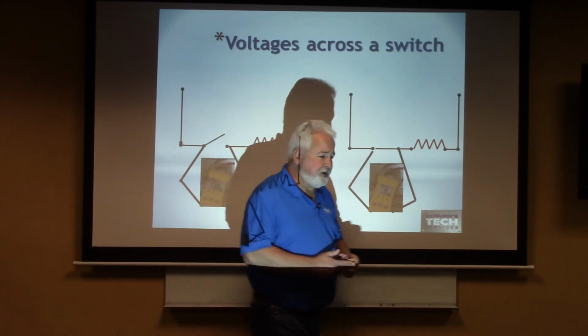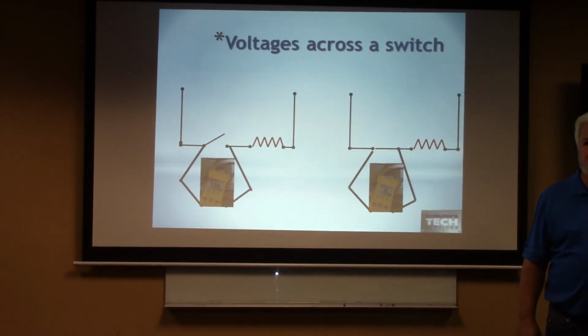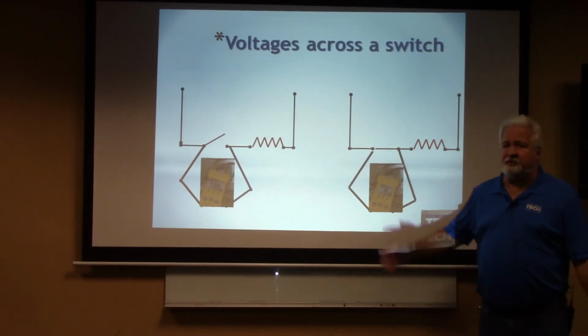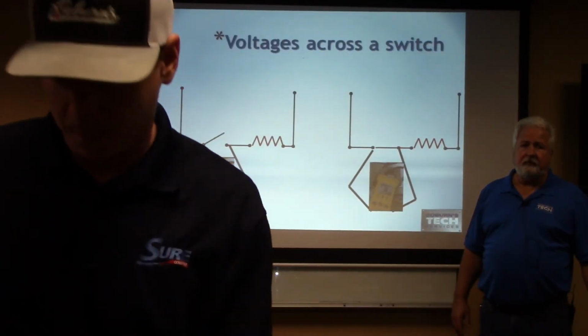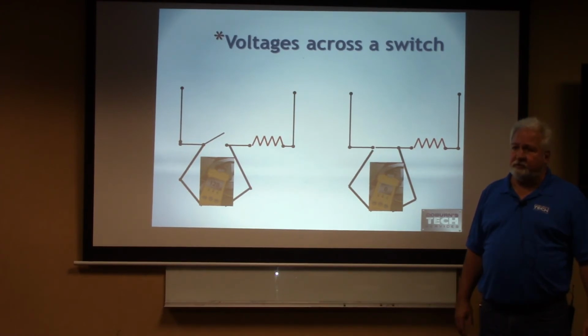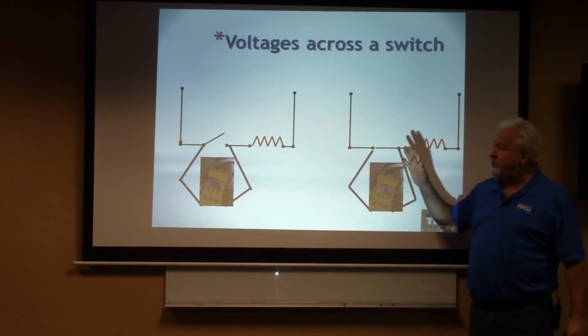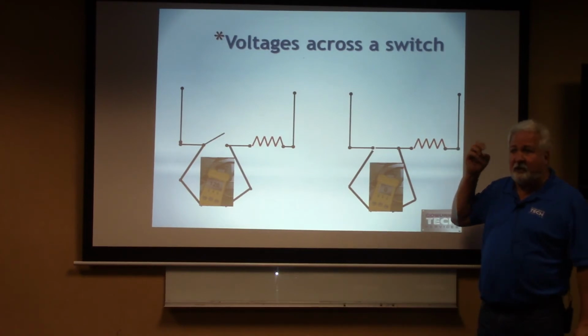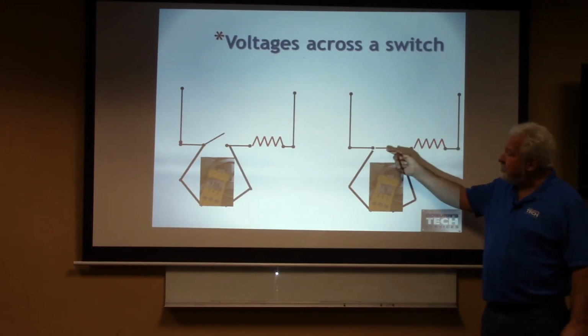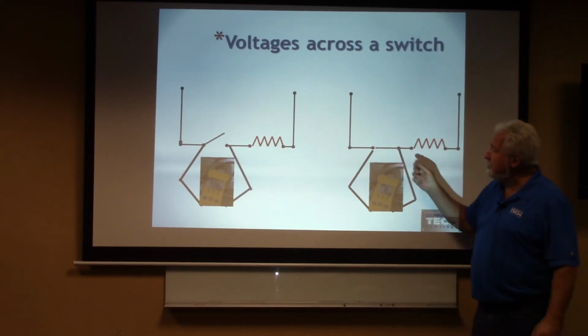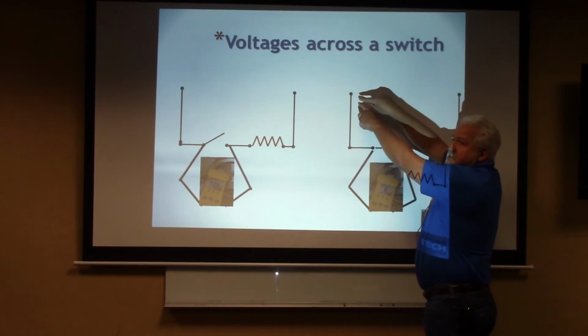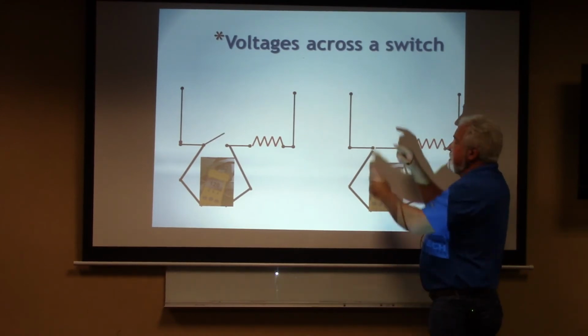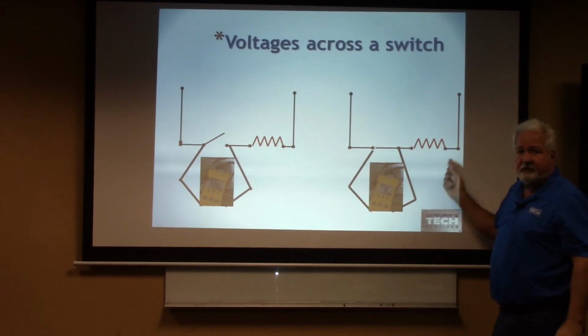Zero. Does it mean I don't have any voltage there? So what do I read across an open switch? What do I read across a closed switch? Zero. Does it mean there's no voltage there? Good. Is that making sense? I know that's a tough one for some technicians to get their head around, and I just want you to see it. If you see it in a picture, sometimes that picture is going to stay in your head, so when you're out on that job site, oh, I got it. So closed switch, you're going to read 0 because I'm seeing the same potential. That's like me taking my meter and putting it just like this. Is that right? It's not going to see. I have to be on the other side of that load for me to see that second potential.